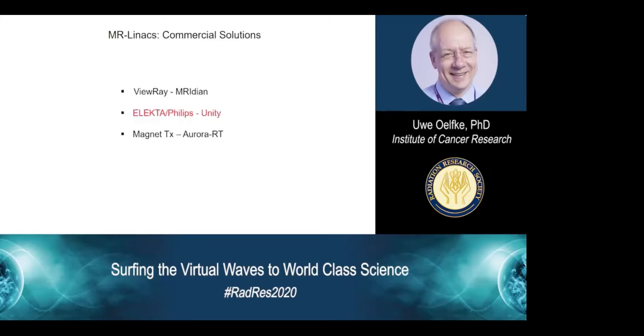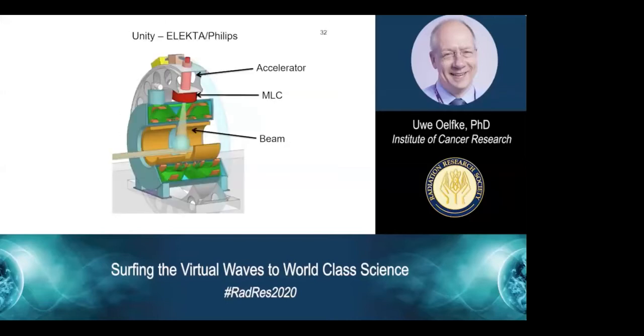Now let's look at the second commercially available platform, the Unity system from Elekta and Philips. Conceptually, I already have explained it. I just briefly want to go through it. Here's the MRI scanner. You can see that the coils in the cryostat have been divided such that there is a window so that the radiation beam can go through this cryostat and irradiate the patient. Then you have the multi-leaf collimator, the linear accelerator, and all this is mounted on a gantry which can rotate around the MRI scanner.